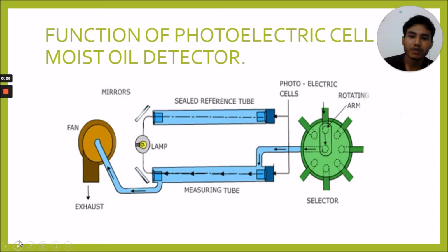It basically comprises two parallel tubes of similar size, each having a photoelectric cell. These are light sensitive and generate an electric current which is proportional to the intensity of the light falling on their surface. Fitted at one end, the lens seal the tube but allow light to pass. Two analytical beams of light from the centrally positioned lamp are reflected by a mirror to pass along the tube to the cell.